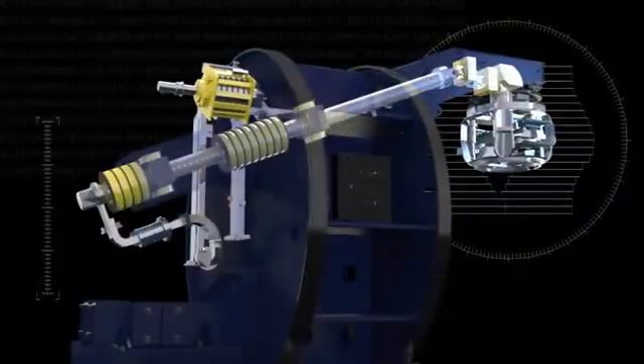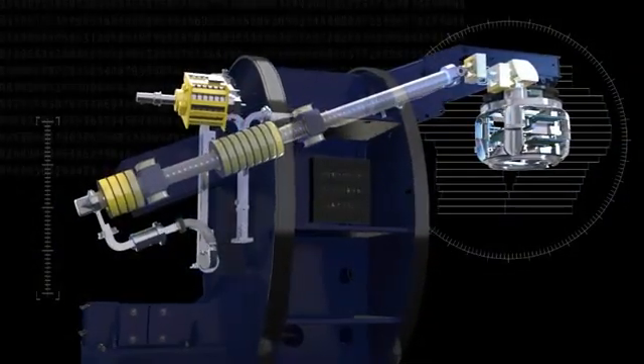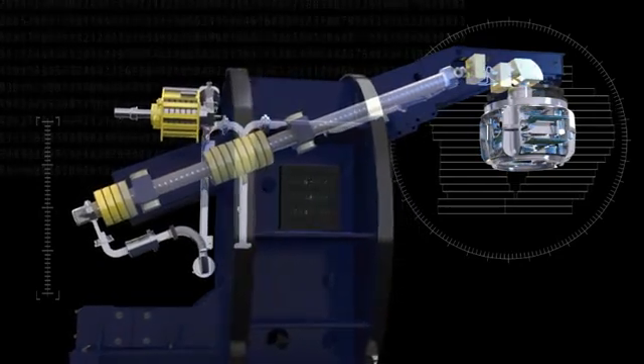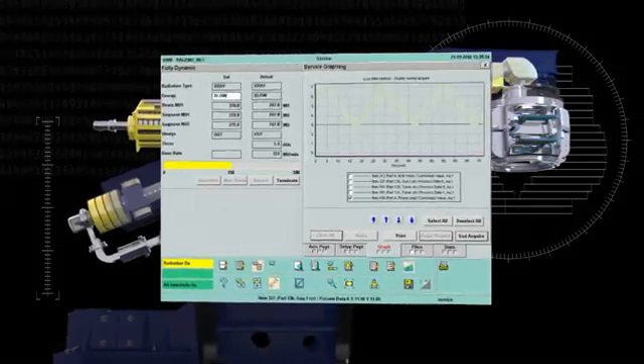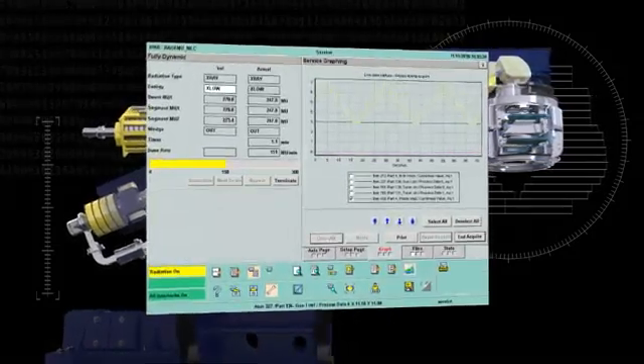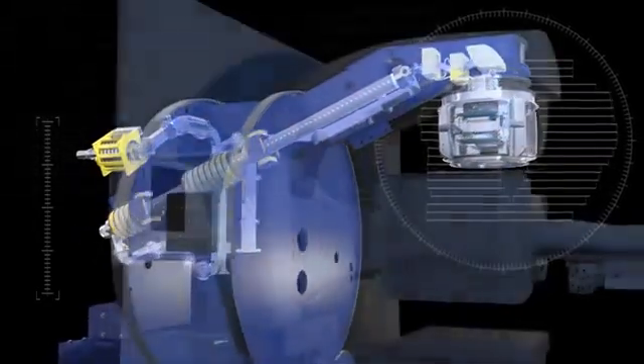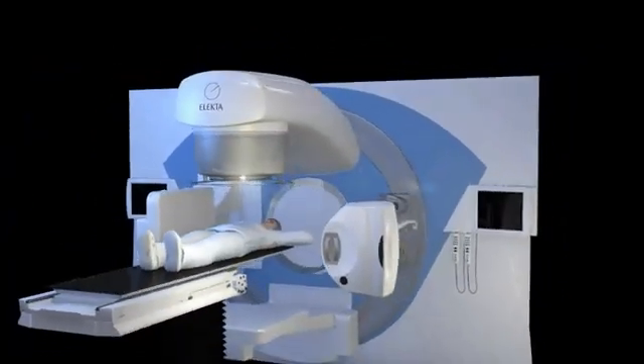All electromagnets, steering and focusing coils are digitally controlled. All mechanical positions of flight tube filters and foils are automatically selected from the control console. And all radiation beam settings are grouped in calibration blocks for each energy. These are stored digitally on the LINAC hard disk for flexible and easy beam adjustment, calibration and servicing.